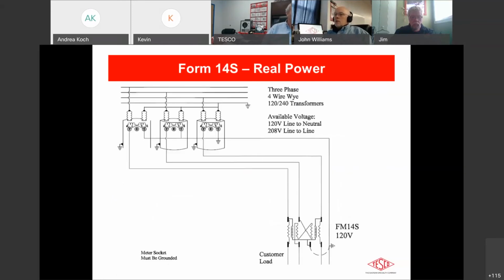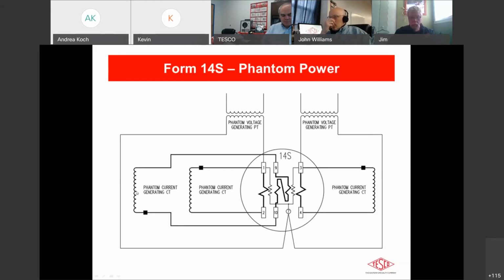So now we're starting to get into the bigger polyphase forms. This here's the 14S. Again, we're similar to the 6 transformer rated. This is its pair in the self-contained. We have that cross-phase element in the middle for the current and the three-phase line coming in. On the meter test board side of things, again, we have the two potential transformers into the two potential elements, the 3 current transformers into those elements.